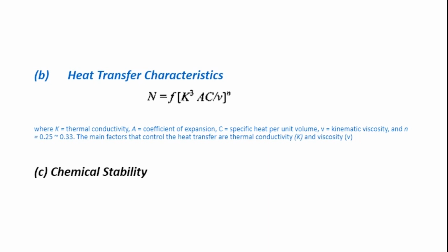Then coming to chemical stability. In service, insulating liquids are subjected to thermal and electrical stress in the presence of materials like oxygen, water, fibrous material, and decomposition products of the solid insulation, singly or in combination. This causes degradation of the liquid, resulting in solid, soluble and gaseous products, which result in corrosion, impairment of heat transfer, and deterioration of the electrical properties.